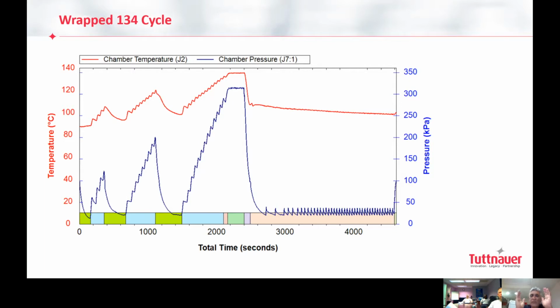So Class B is the process. And in order to comply with this process, there are two conditions. The first condition is being able to remove more than 99% of the air at the beginning of the cycle. Just for your information, the machines we know until now, except the Elara, which is Class B, I'm talking about all the Easy and MK models, those machines which are gravity models, are able to remove between 90 to 95% of the air. It means we stay with 5 to 10% of air inside the chamber at the beginning of the sterilization stage. Is that clear? So when we come to the Class B cycle, we are looking to get rid of more than 99% of this air.